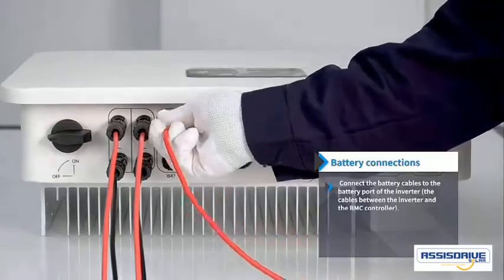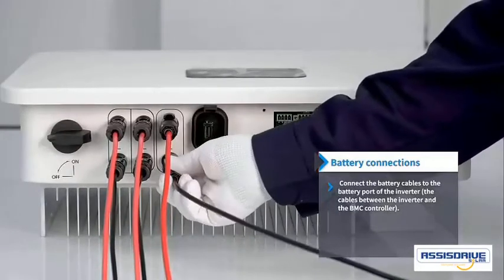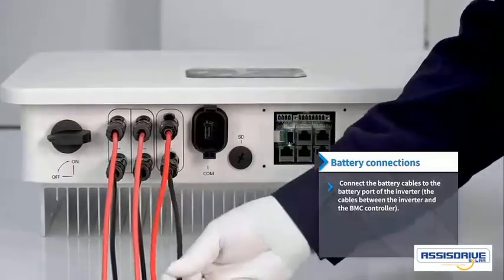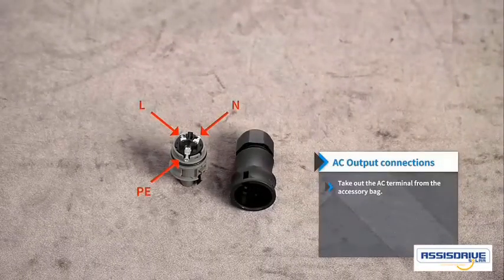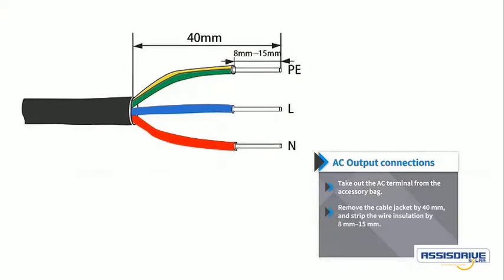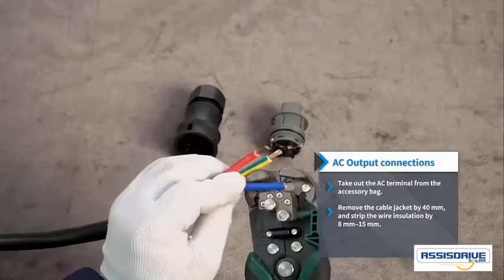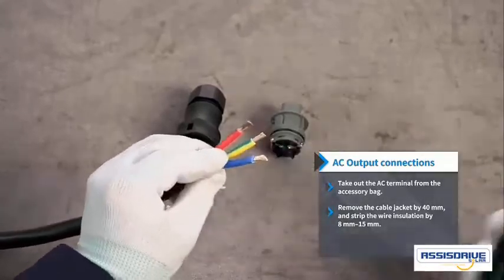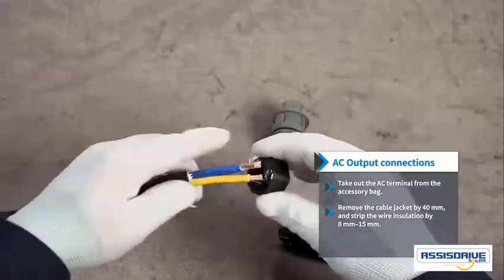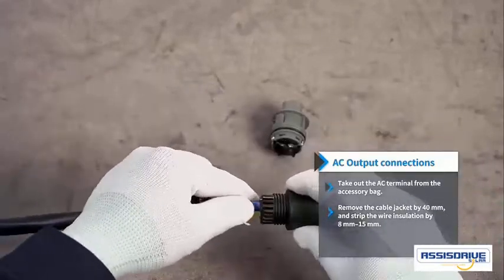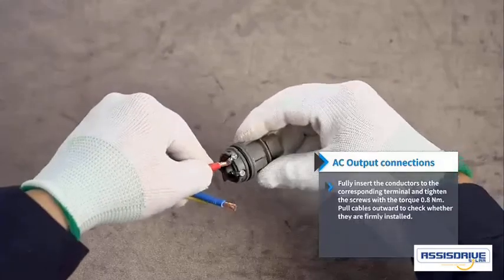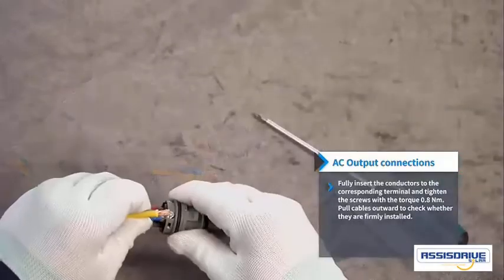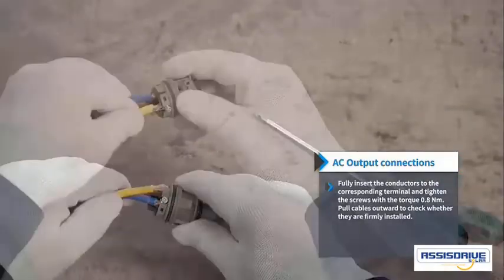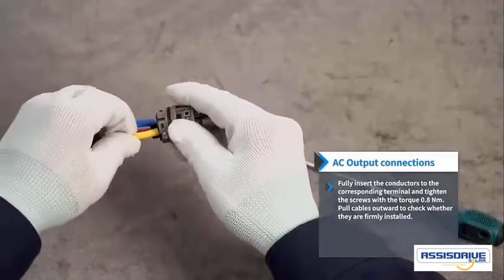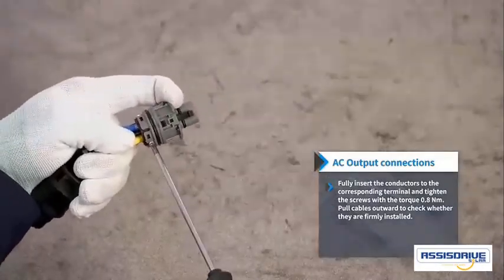Connect the battery cables to the battery port of the inverter, the cables between the inverter and the BMC controller. AC output connections. Take out the AC terminal from the accessory bag. Remove the cable jacket by 40 mm and strip the wire insulation by 8 mm to 15 mm. Fully insert the conductors to the corresponding terminal and tighten the screws with the torque 0.8 Nm. Pull cables outward to check whether they are firmly installed.